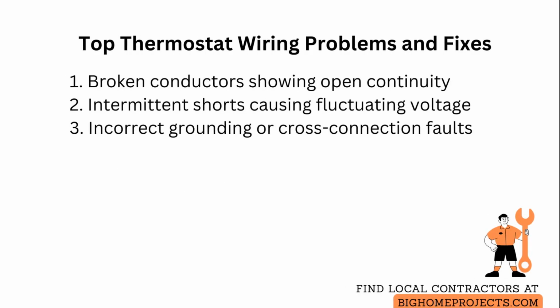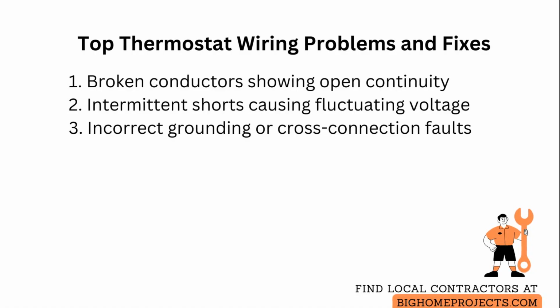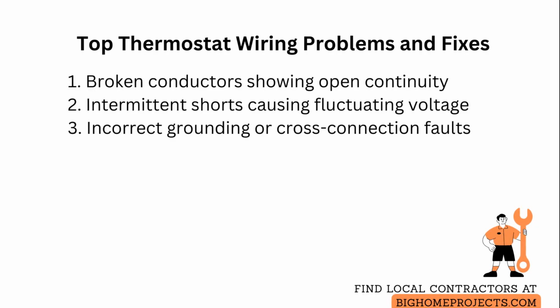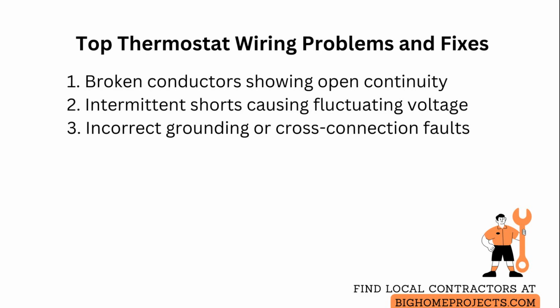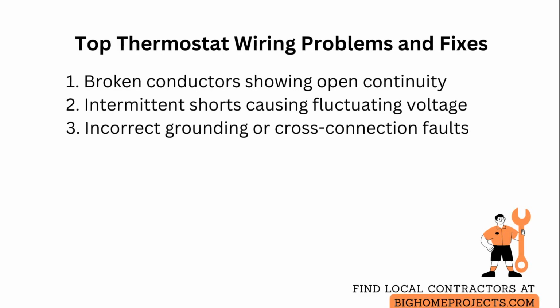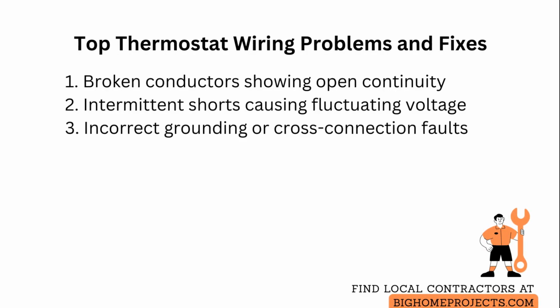Three common issues are broken conductors that show open continuity, intermittent shorts that cause fluctuating voltage, and incorrect grounding or common wiring that backfeeds the circuit. Fix broken conductors by replacing or splicing with proper low voltage thermostat cable using soldered joints or rated mechanical connectors and insulating with heat shrink tubing.